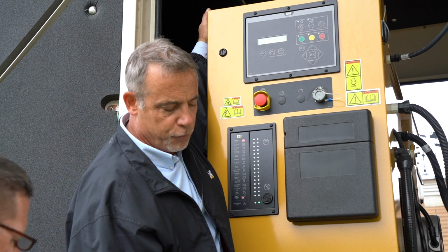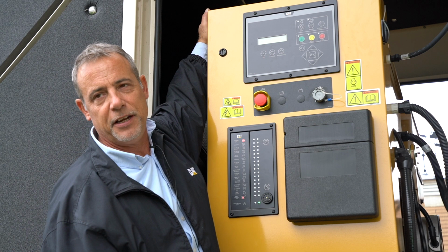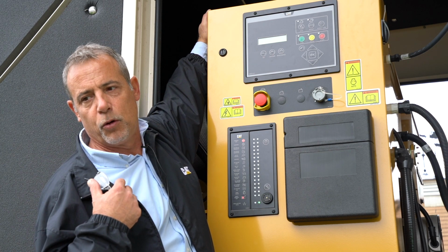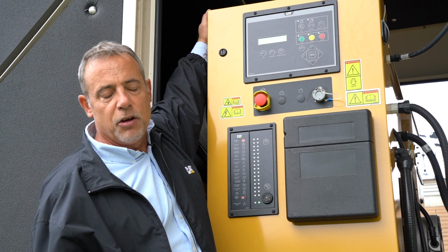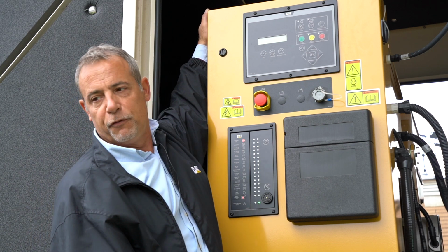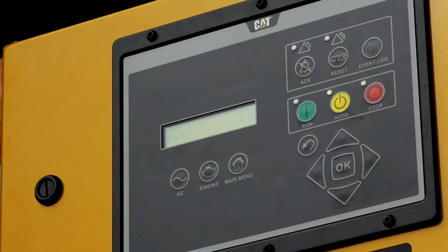You have a 1,400 gallon tank, so you're not going to have an issue with it overheating. Plus it also has a fuel cooler on it, so you really shouldn't have a problem. The only time you would see a problem is if you get low on fuel and the radiator's clogged up. Then you're going to run a high fuel temperature.